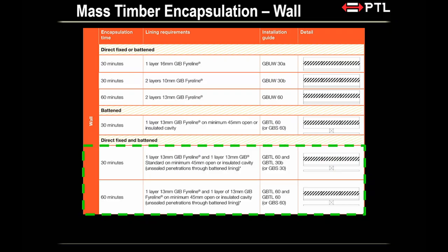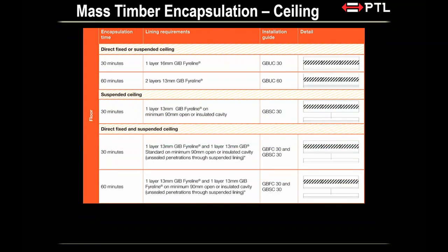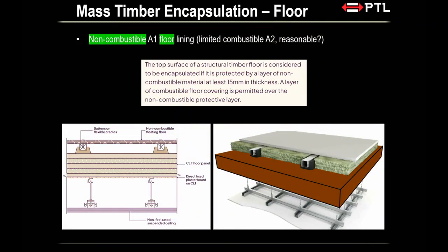This particular system here just allows your services to run freely, unsealed penetration, right? Similarly for floor, okay, direct fix, suspended ceiling system. Now when we talk about, so that's ceiling. Now when we talk about floor, it's actually the top side of the floor, right? On the top side of the floor, there's also an encapsulation solution, and typically that's with a non-combustible lining going over the CLT floor. You have to be at least 15 mil thick.